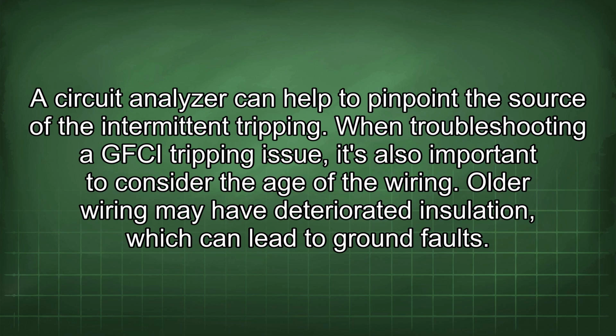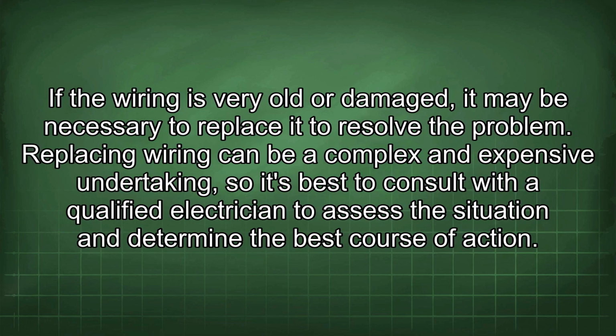When troubleshooting a GFCI tripping issue, it's also important to consider the age of the wiring. Older wiring may have deteriorated insulation, which can lead to ground faults. If the wiring is very old or damaged, it may be necessary to replace it to resolve the problem. Replacing wiring can be a complex and expensive undertaking, so it's best to consult with a qualified electrician to assess the situation and determine the best course of action.